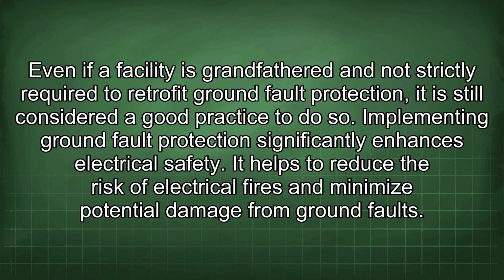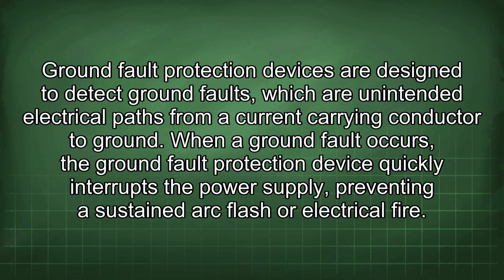Even if a facility is grandfathered and not strictly required to retrofit ground fault protection, it is still considered good practice to do so. Implementing ground fault protection significantly enhances electrical safety. It helps to reduce the risk of electrical fires and minimize potential damage from ground faults. Ground fault protection devices are designed to detect ground faults, which are unintended electrical paths from a current carrying conductor to ground. When a ground fault occurs, the device quickly interrupts the power supply, preventing a sustained arc flash or electrical fire.